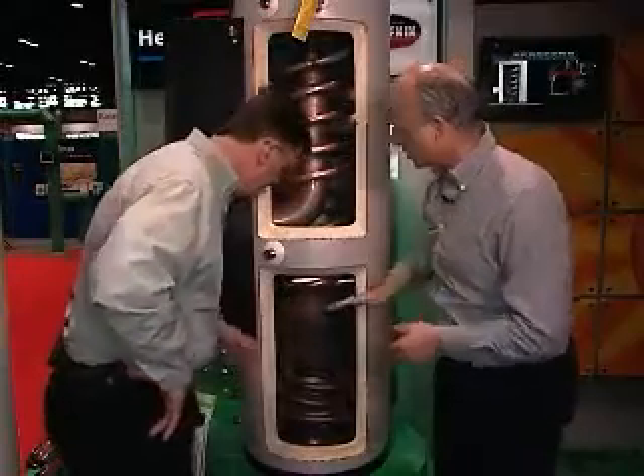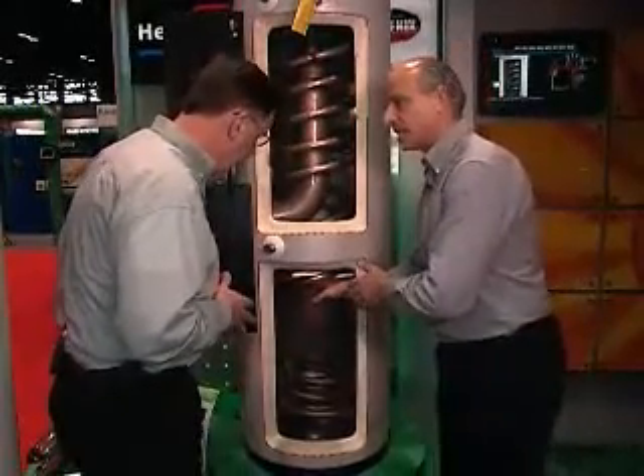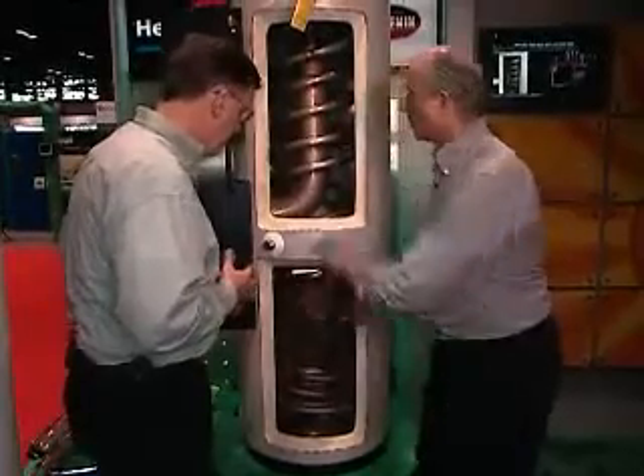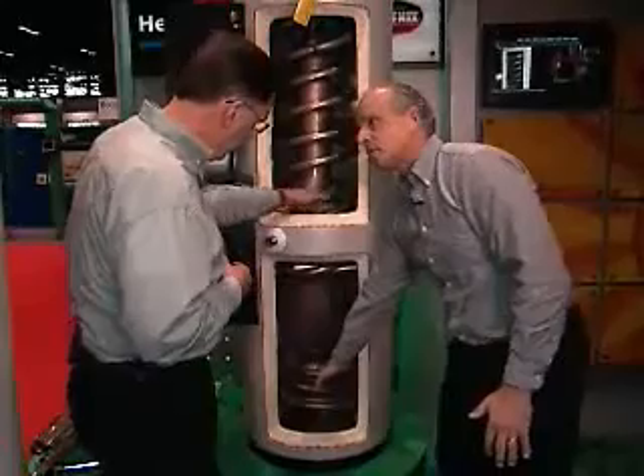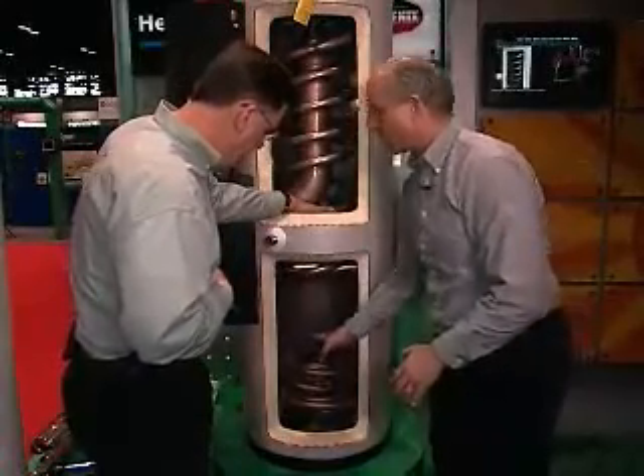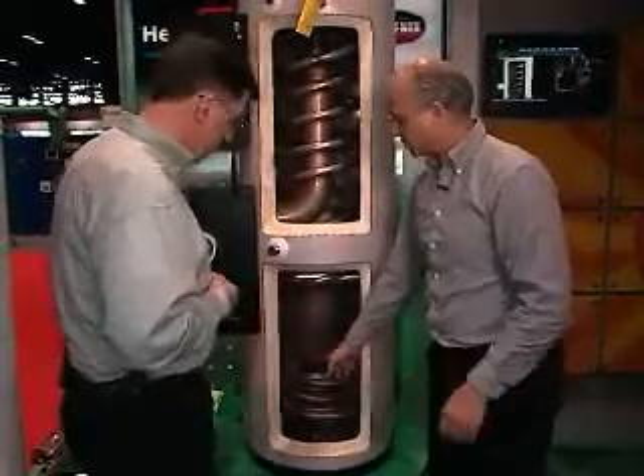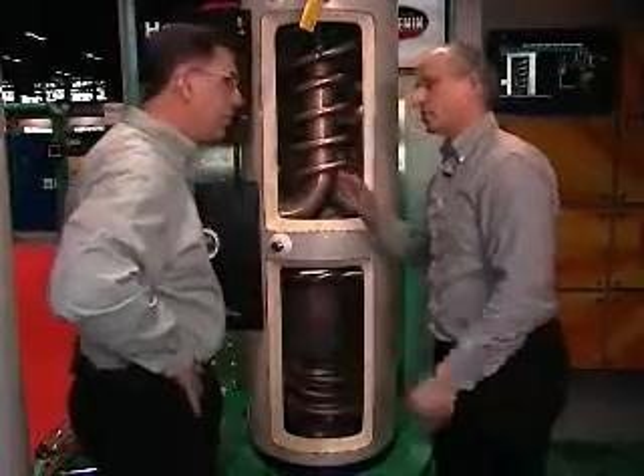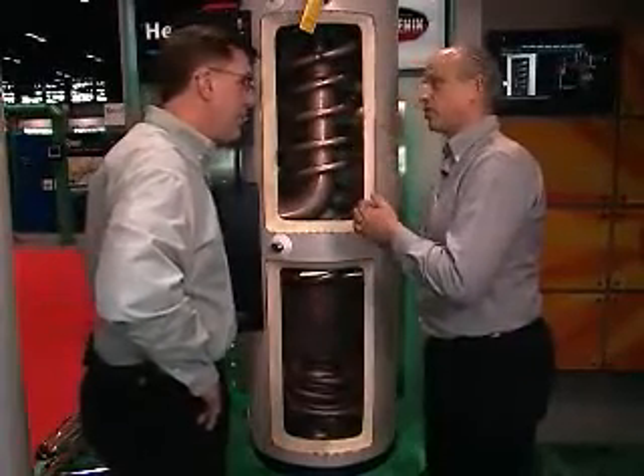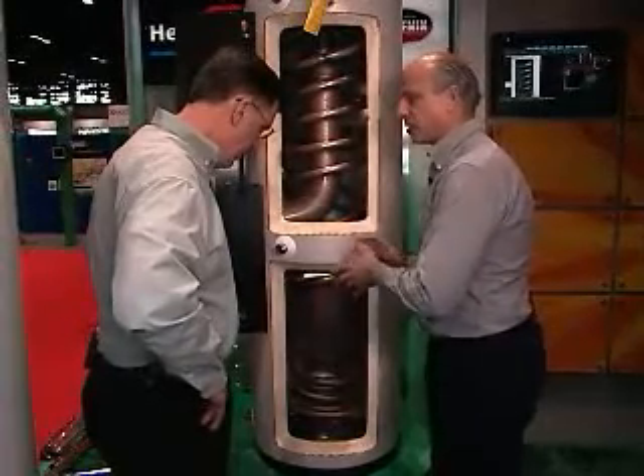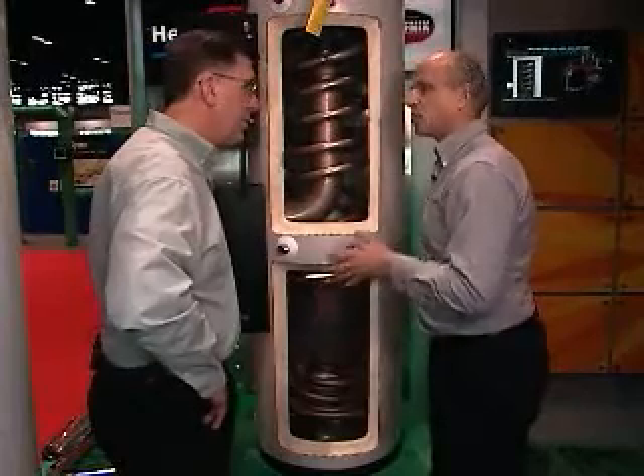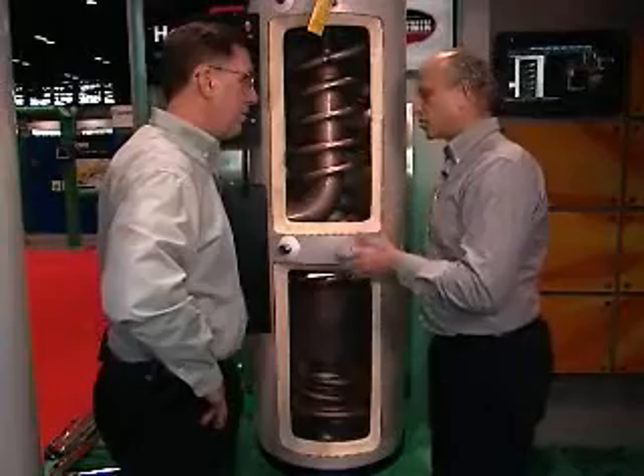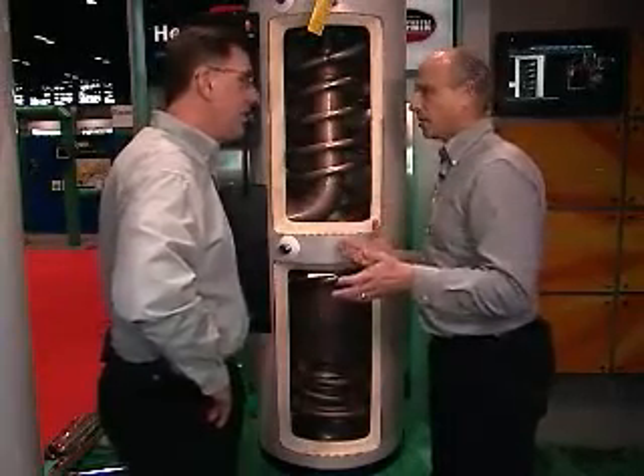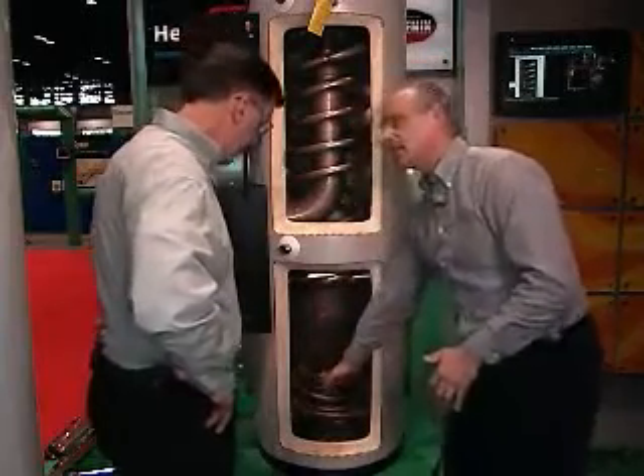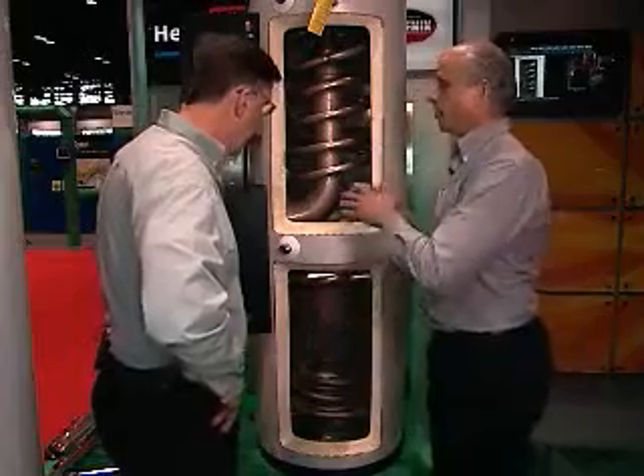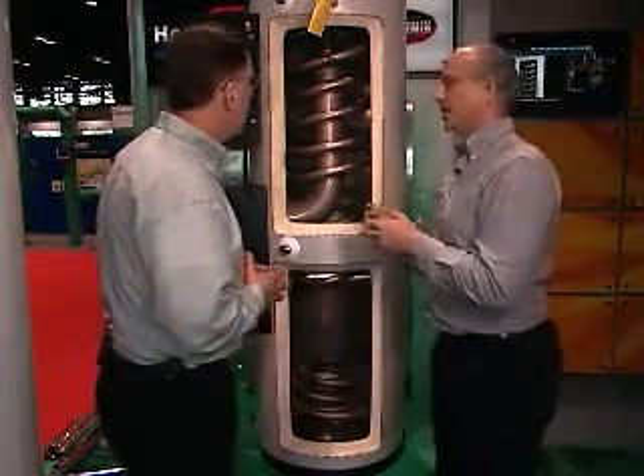for the living space. Essentially we have a bivalent tank, two segments of the tank. We keep the coldest water on the bottom and only heat the top portion, so we're getting optimal performance on the solar. Right, that's what you want to do. One of the things we've added, through the electronics in our system, is that we modulate the pump on the solar to the solar panels, so we maximize the efficiency of the solar panels that you attach to your roof. This is the first integrated hydronic system out in the marketplace that really simplifies the installation. Our goal is to open up solar to the hydronic world without a lot of complication, really pre-packaging everything, having an easy tie-in to your solar, and letting the solar heat the tank up and give you hot water and some marginal benefit on the heating side.